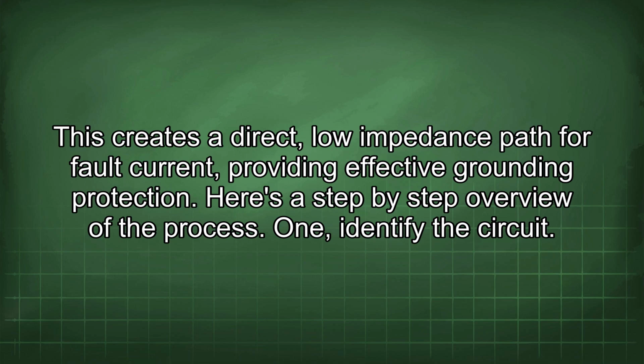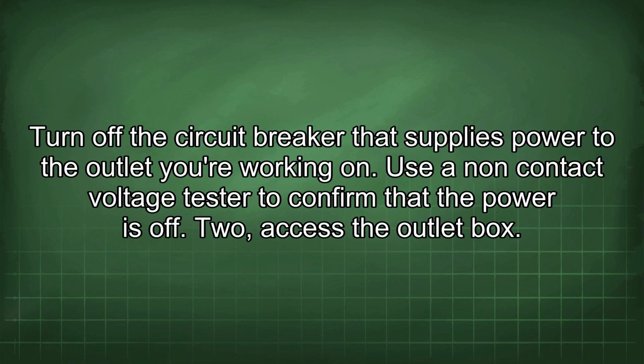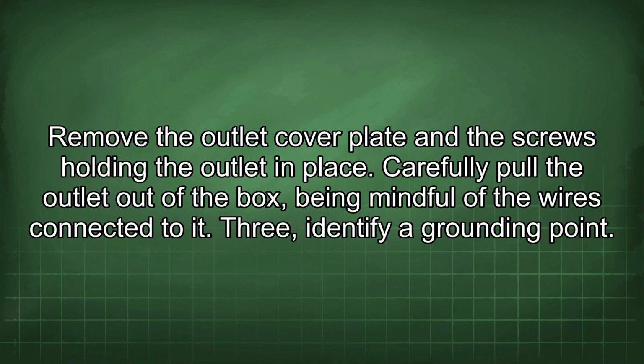Here's a step-by-step overview of the process. 1. Identify the circuit. Turn off the circuit breaker that supplies power to the outlet you're working on. Use a non-contact voltage tester to confirm that the power is off. 2. Access the outlet box. Remove the outlet cover plate and the screws holding the outlet in place. Carefully pull the outlet out of the box, being mindful of the wires connected to it.